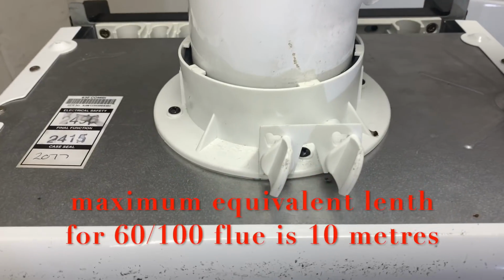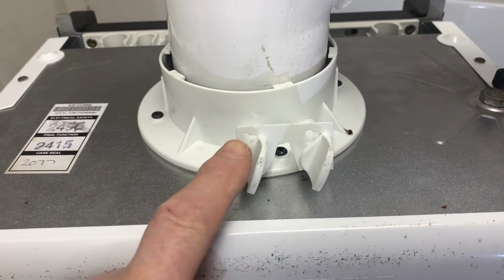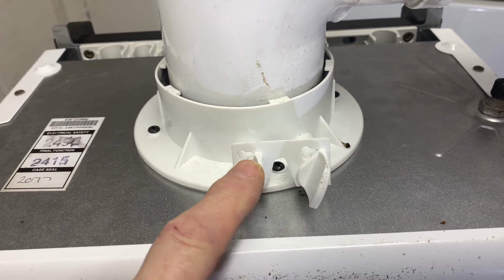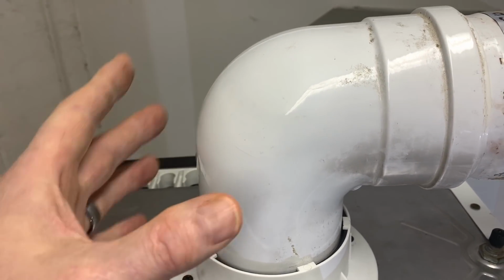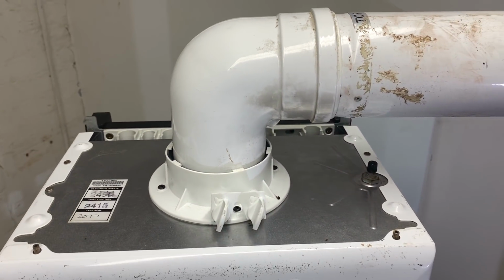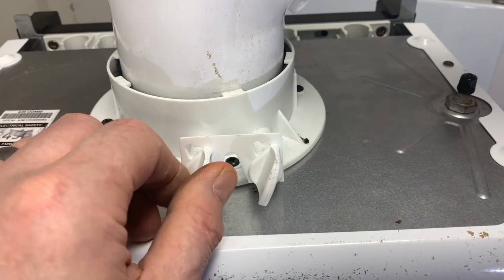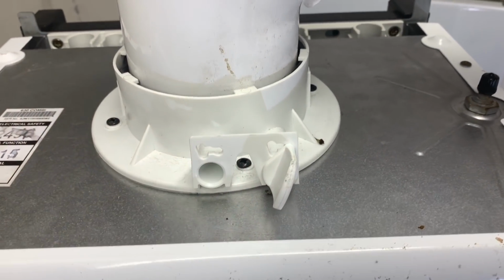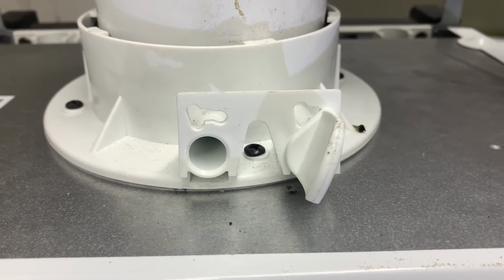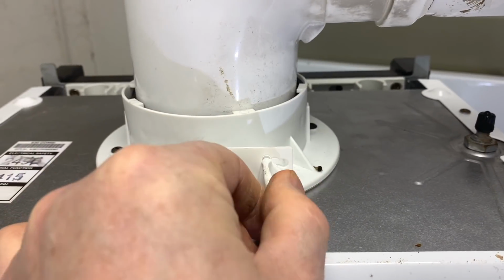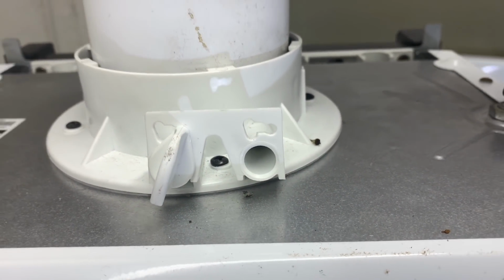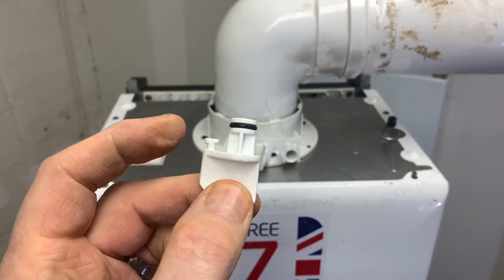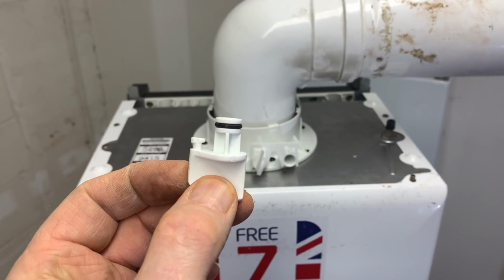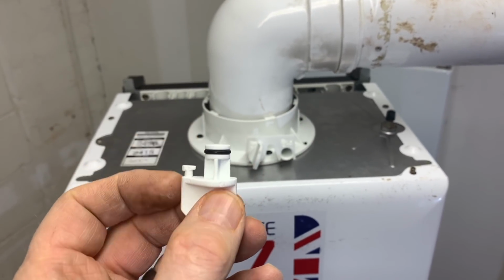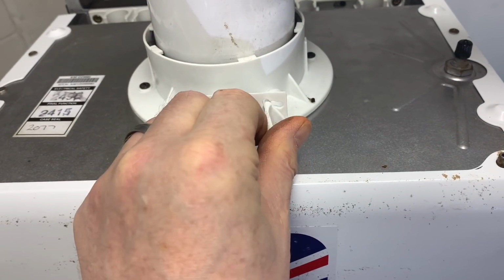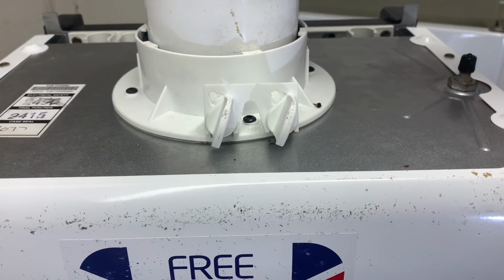Now the turret itself is one of what I call the better ones, because the test points are at the front of the boiler, not on the elbows, where if the elbows turn to the side, it's hard to get your analyzer in. But this little one here, test point here, that's where you do your products of combustion test. And obviously that makes this one your flue integrity test one. Now one of the things I found out with these little plugs is this little lug here can snap off quite easily. So just be aware of that. And always lubricate the O-ring before you put it back to make it easier next time you're doing your service.